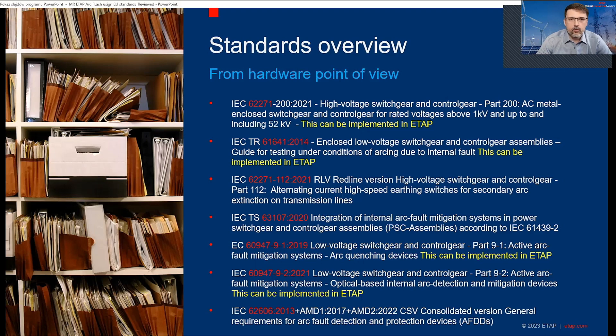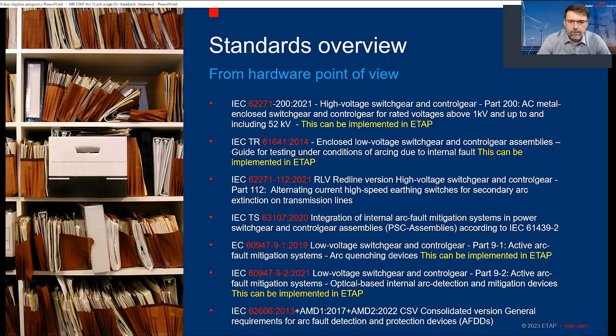Then we have IEC 62271-112, an interesting topic about high voltage switchgear and ultra-fast earthing switches, which comes up more often in transmission and medium voltage switchgear. There is IEC Technical Standard 63107, which talks about integration of arc flash mitigation systems into power switchgear assemblies. And there is IEC 60947, which talks about arc quenching devices — if you have an arc quencher, there's now a standard about it, and you should implement it in ETAP.